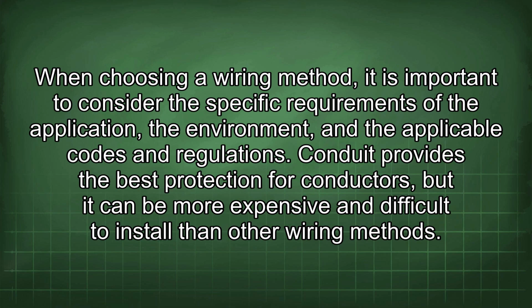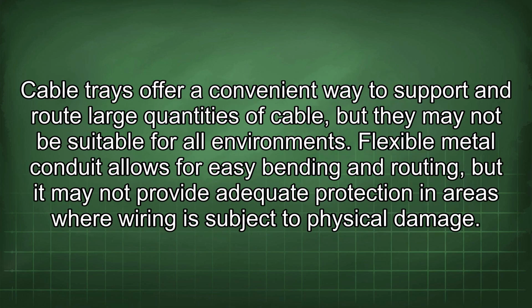When choosing a wiring method, it is important to consider the specific requirements of the application, the environment, and the applicable codes and regulations. Conduit provides the best protection for conductors, but it can be more expensive and difficult to install than other wiring methods. Cable trays offer a convenient way to support and route large quantities of cable, but they may not be suitable for all environments. Flexible metal conduit allows for easy bending and routing, but it may not provide adequate protection in areas where wiring is subject to physical damage.